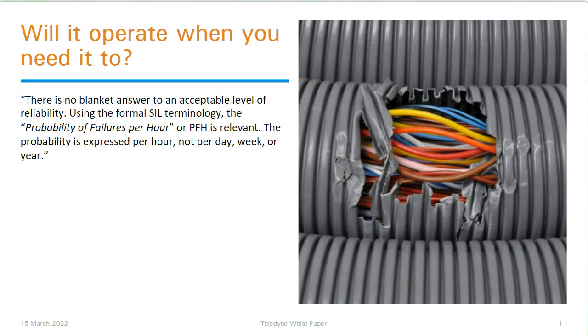This whole concept of probability of failure on demand is really all about saying, if I need that thing to work, if I need my sprinkler system to come on, if I need that alarm to work and warn people, what are the chances of it actually working when I need it to? Or what are the chances that it will be broken? And we can think about some scientific terminology here related to probability of failures per hour. We could also, for example, express it as probability of failures per day or week or year. But in the context of SIL terminology, the probability of failures per hour, or the PFH, is the relevant terminology.